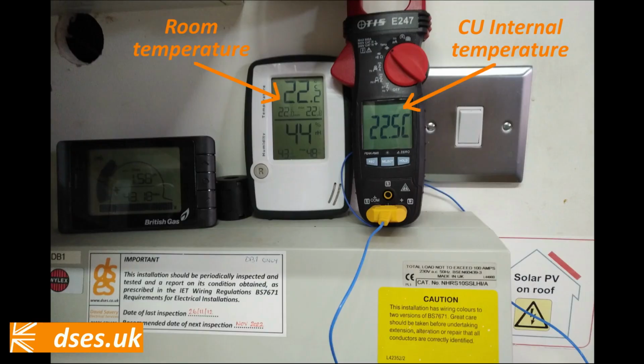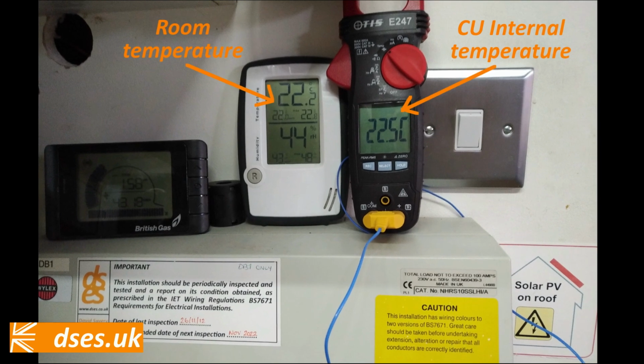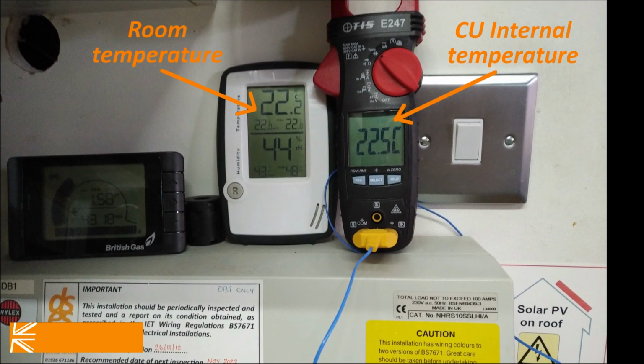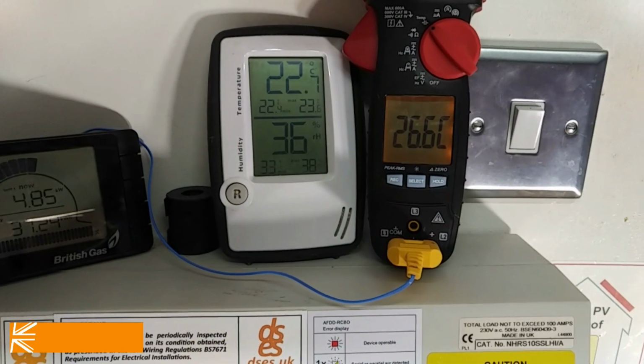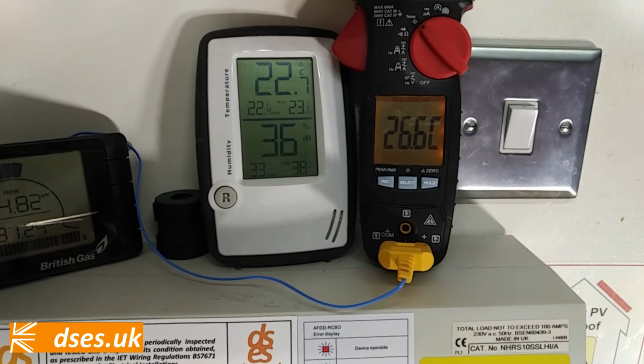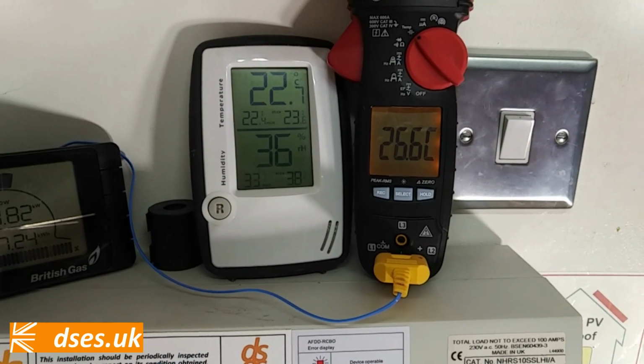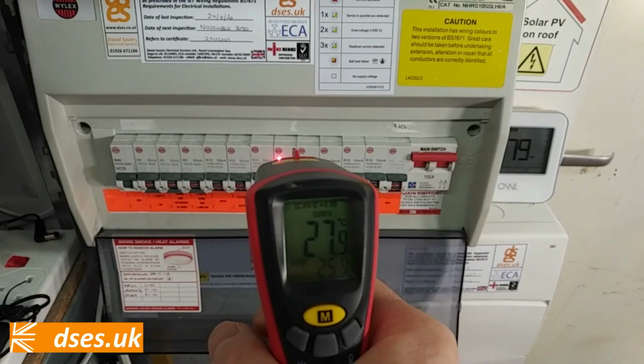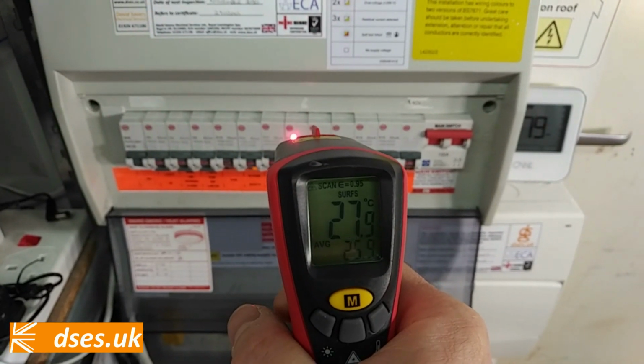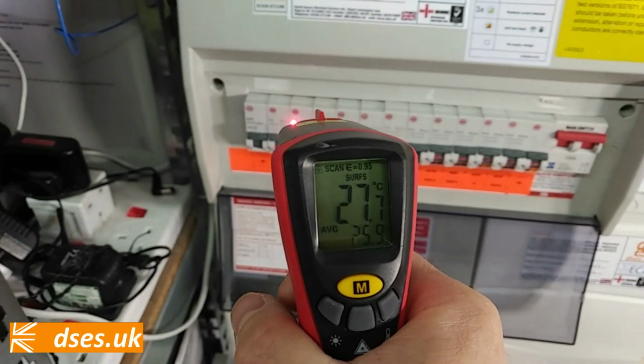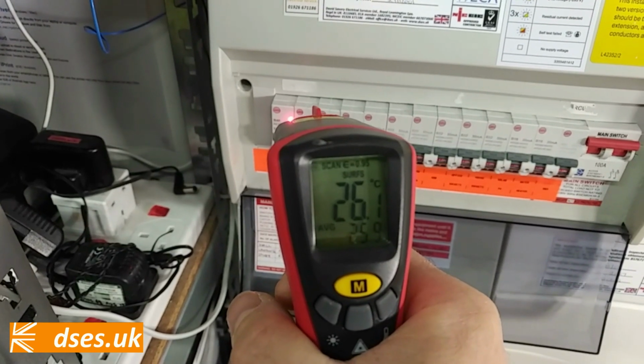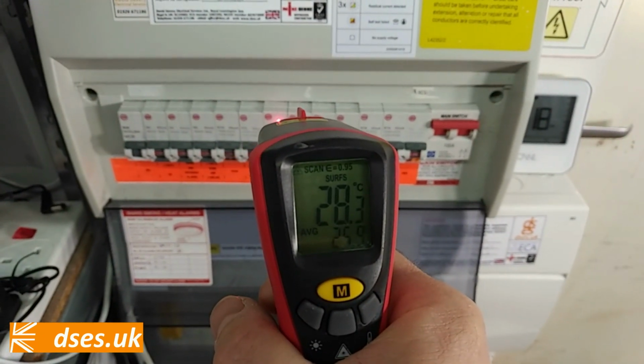If I upload a video in 6 months showing some of these reporting a failed self-test, well then that will probably speak volumes, but part of the experiment here is to see what the heating effects are. Prior to conversion, the interior of the dual RCD configuration was around that of room temperature. Now that it's been in and operational for a week, I can report the internal temperature is a few degrees higher, no real surprise there. Using a laser thermometer, we can see the AFDDs show a higher surface temperature than the simpler devices like the main switch, MCBs and RCBOs.